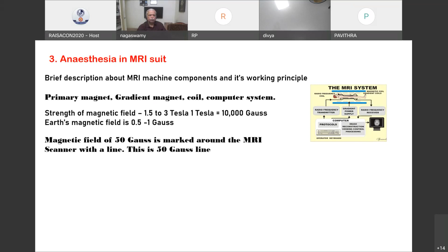So any equipment going very close to this, within this line, will have a ferromagnetic attraction. If it is a credit card or your ID badges or any metal-containing things, they will all be sucked in and fly and cause trauma. Whereas the 5 Gauss line is safer, so your anesthesia machine can be placed here. It should not go inside. And your anesthesia machine should be MRI compatible and not just MRI safe. Because as I told earlier, if a machine is safe, it will not be attracted, but it will not be functioning properly.